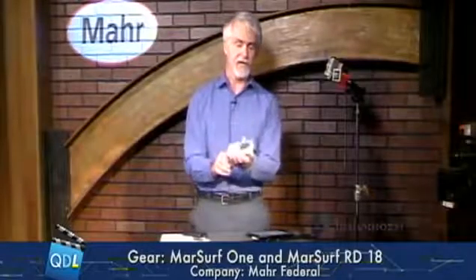Let me show you. I need to do a calibration on this. I rotate the probe 180 degrees and retract it back inside — I'm ready to do a calibration. I click Calibrate on the bottom and it comes up. First it asks what kind of calibration I'm doing: I have my choice of RA or RZ. I simply look on the bottom of the device and it tells me we're going to do an RZ measurement and the reference is 9.46 microns. So I come back, select RZ, and type in 9.46. I tell it how many passes I want — just one pass to keep things moving.